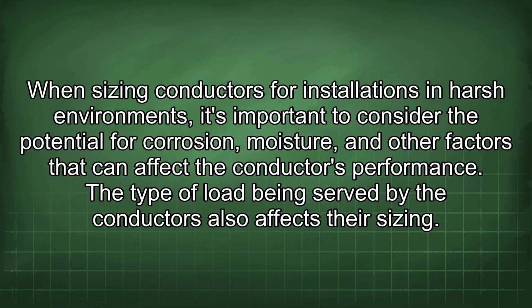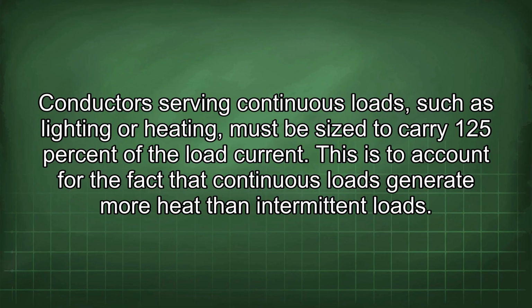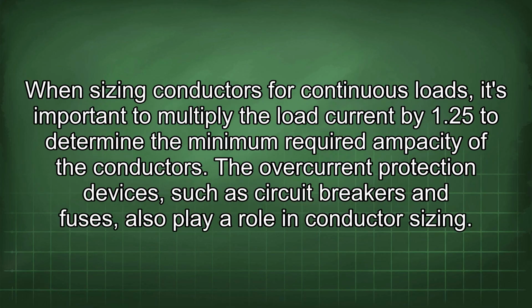The type of load being served by the conductors also affects their sizing. Conductors serving continuous loads, such as lighting or heating, must be sized to carry 125% of the load current. This is to account for the fact that continuous loads generate more heat than intermittent loads. When sizing conductors for continuous loads, it's important to multiply the load current by 1.25 to determine the minimum required ampacity of the conductors.